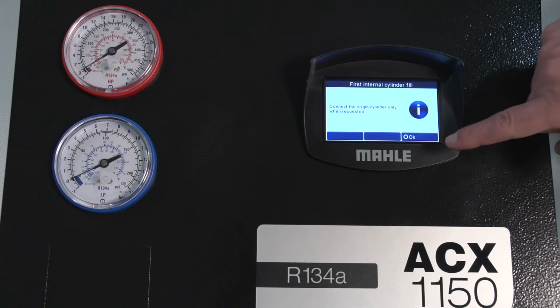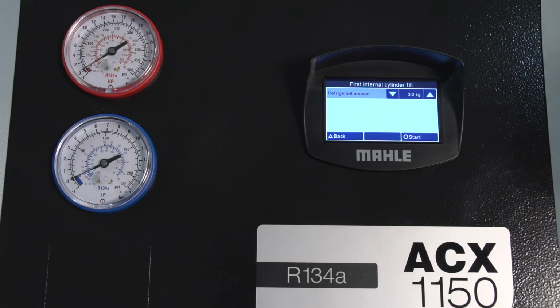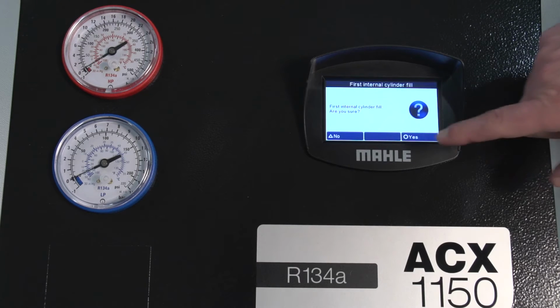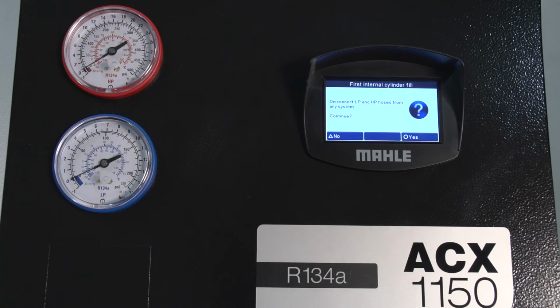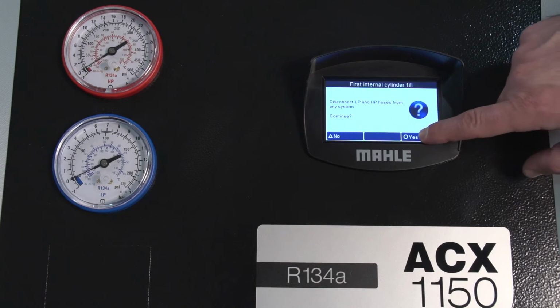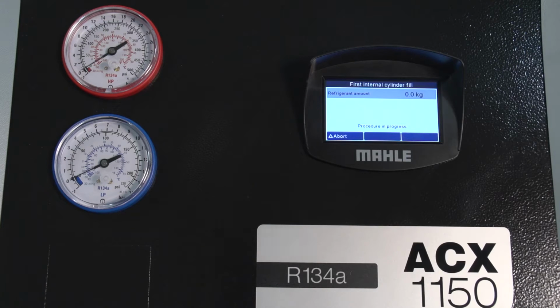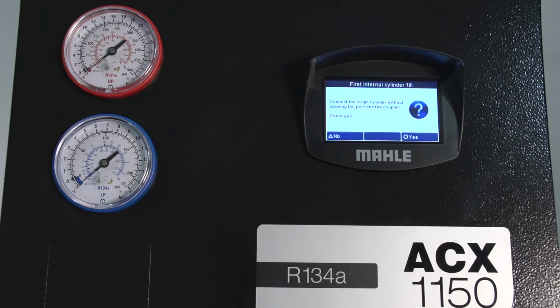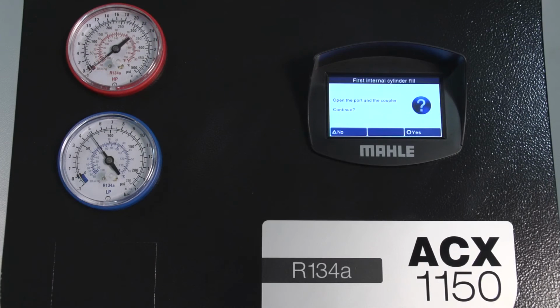Set the internal cylinder fill to the desired quantity with a minimum of 3 kilograms. Follow the on-screen instructions. Make sure the hoses are disconnected from any external source. Start the procedure that initially creates vacuum in the internal refrigerant circuit. This process takes approximately 15 minutes. Once the message is displayed, the unit can be connected to the external cylinder and the valves opened.